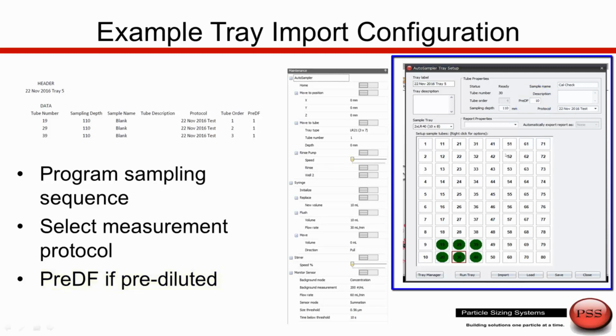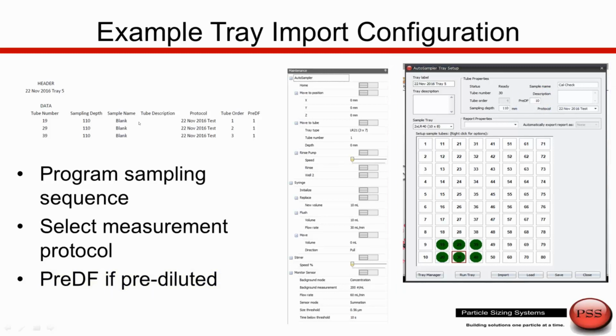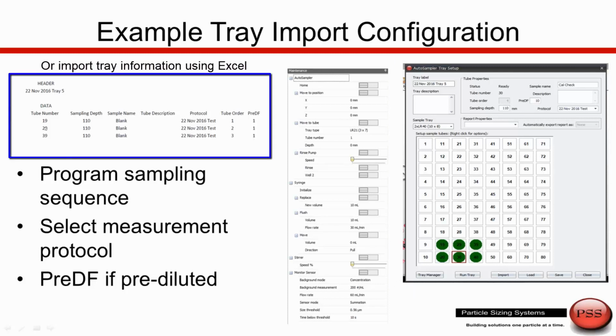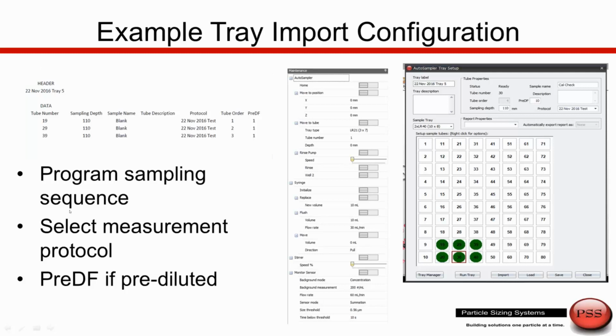So we could program the system using the software as you see here, or if we're doing larger trays, sometimes it's actually easier to enter the data into an Excel spreadsheet, and that's what we see up here. We could take an Excel spreadsheet, enter the information for each of the tubes, and then import this either as an Excel spreadsheet or CSV file, and then the system will take the data into here and feed that into the protocols in the system. So these are the different ways which we can program the tray prior to the measurement, and we could use the same protocol for each tube or use multiple protocols for different samples.